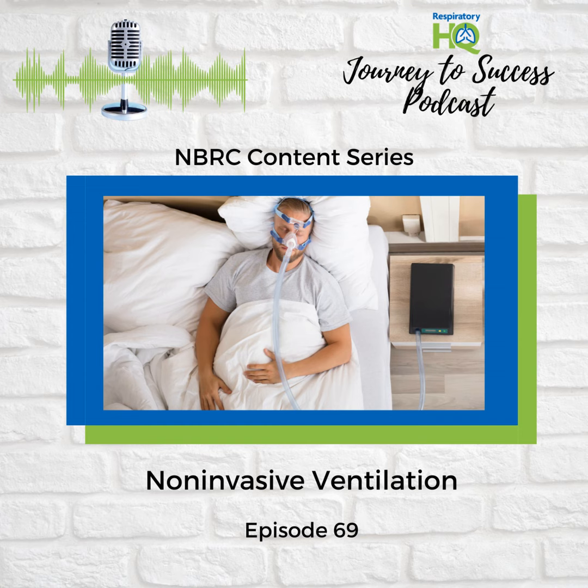Simple enough. BiPAP must be more complex with its 2 pressures. It is a bit more involved, yes. For BiPAP, you have 2 pressures to set, EPAP and IPAP. Right, expiratory and inspiratory. The EPAP, the expiratory pressure, is often started around 5 to 8 centimeters H2O. Remember, this helps with oxygenation and keeping airways open.